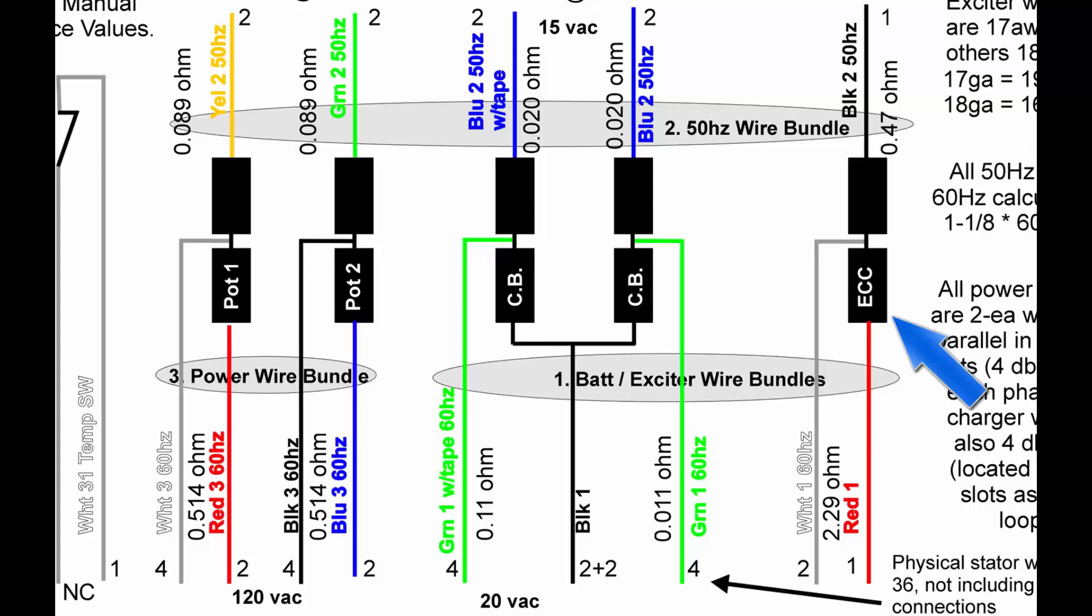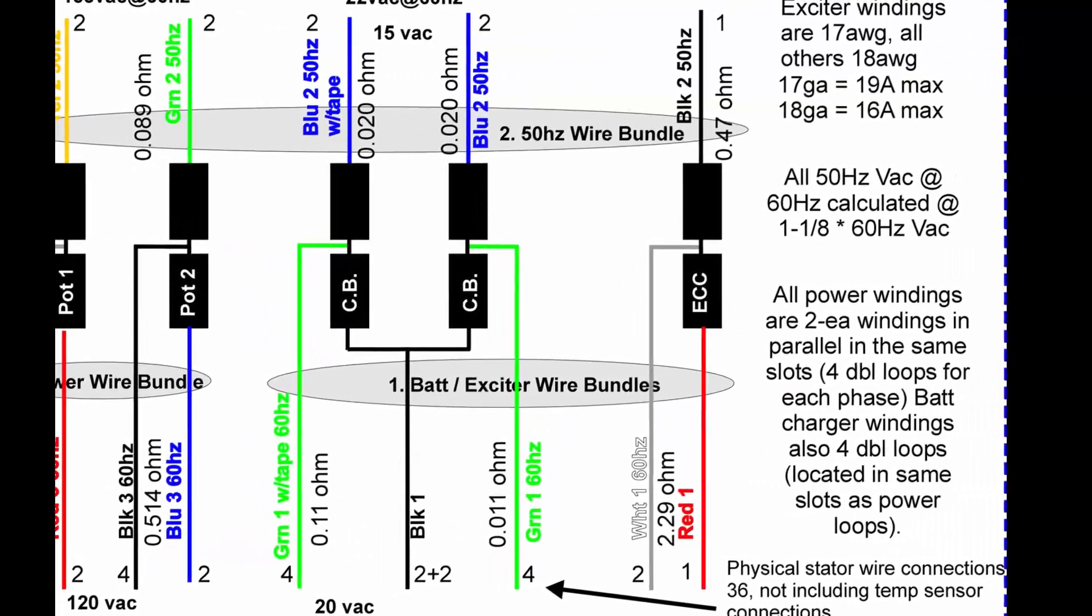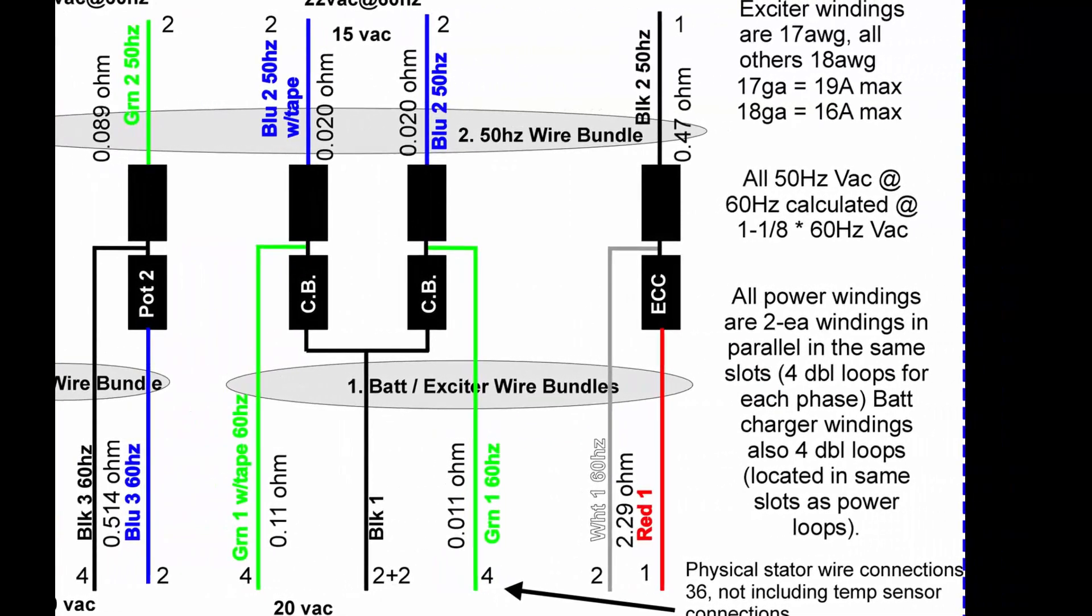And last but not least, we also have the exciter winding on the right-hand side labeled ECC. It's also 50 Hz or 60 Hz capable. Once again, red one to white one is for 60 Hz, and red one to black two at the top is for 50 Hz.